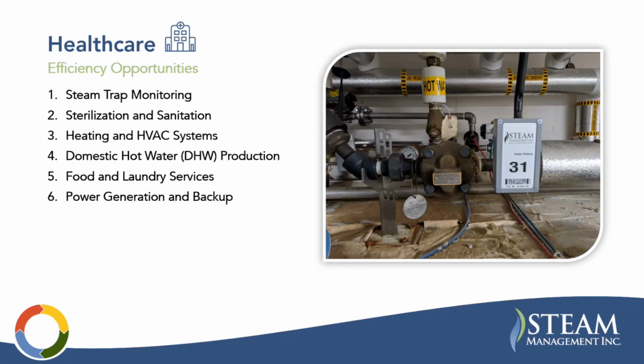Efficiency opportunities here, steam trap monitoring. This is, again, a big one, and healthcare is probably one of the spaces that we see this the most. They just have higher pressure lines. They have sprawling steam systems, a lot of different users, a lot of different steam traps. Generally, maybe a maintenance crew that's stretched thin, and steam trap monitoring gives them more insight into the health of their steam trap population and what needs to be addressed.